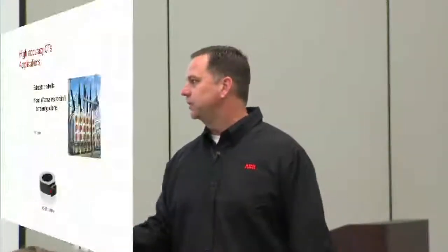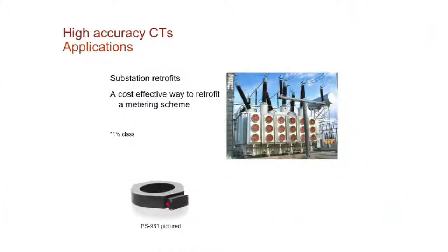And the only way they can recoup their investment is to actually have those turbines spinning, generating electricity, and having the utility purchase that. Okay? So they want to get as much billing, okay, that they possibly can. That's how they recoup their investment. So we have very, very specific current transformers designed for applications like that as well. It's a great use of that wide range that we talked about, from 1% of nominal current all the way to the highest rating. Substation retrofits is another big one.